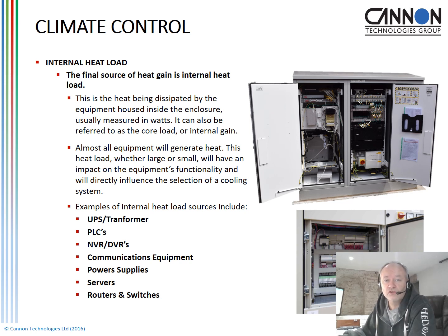Almost all equipment will generate some sort of heat, whether it's a small or a large piece of equipment, and it will have some impact on the thermal management and how much cooling is required. Typical examples of heat loads which might be installed in your cabinet are a UPS, a transformer, PLC equipment, network video recorders, digital video recorders, any communications equipment, power supplies, servers, routers and switches. As I said, all of these units will produce some kind of heat, even fiber optic switching equipment.